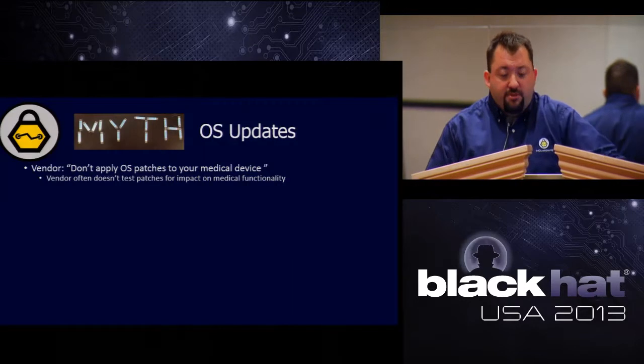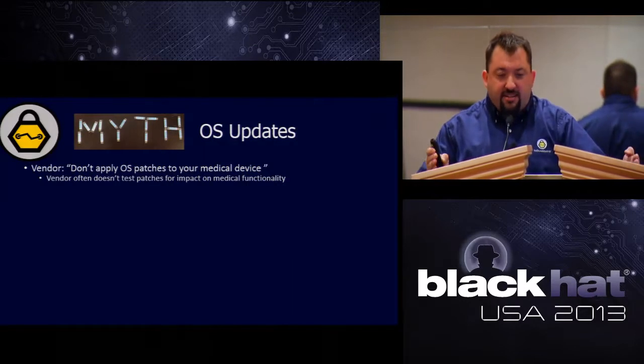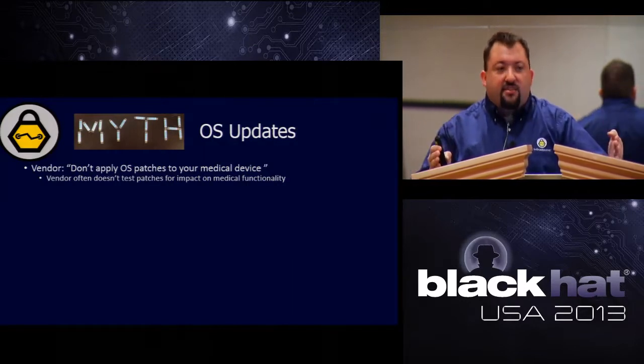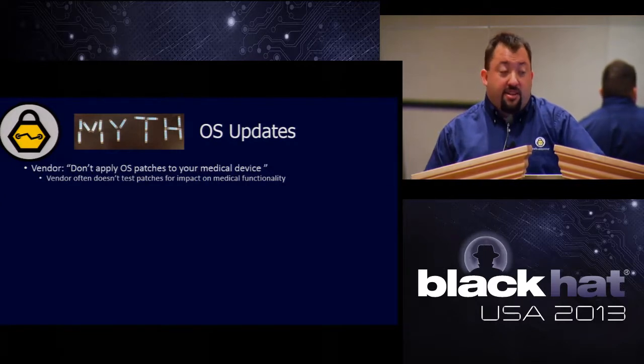So you set up your system at that time, that's how they tested that system. It's got to stay like that, you can't make those changes. Because if you change this library, the argument is, what if the device stops working the way it's supposed to and cooks your patient, like an MRI machine?